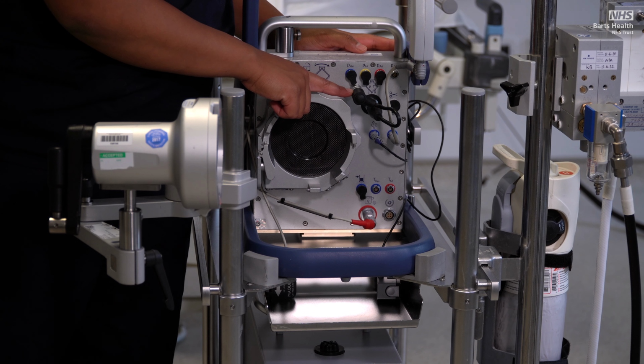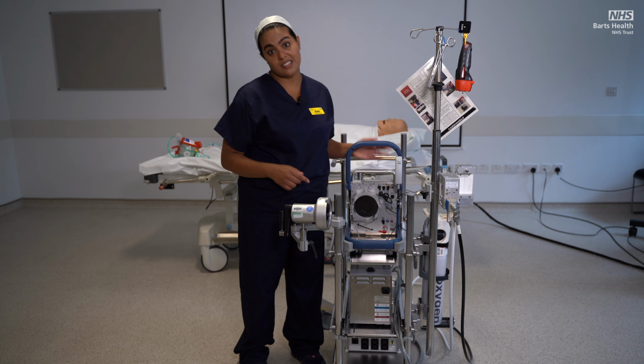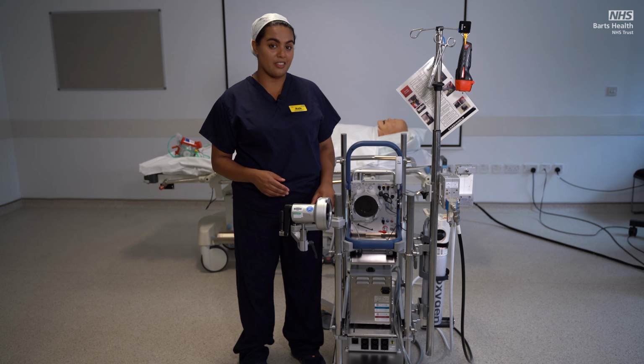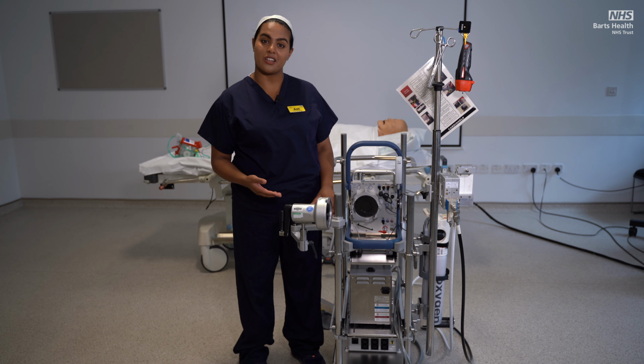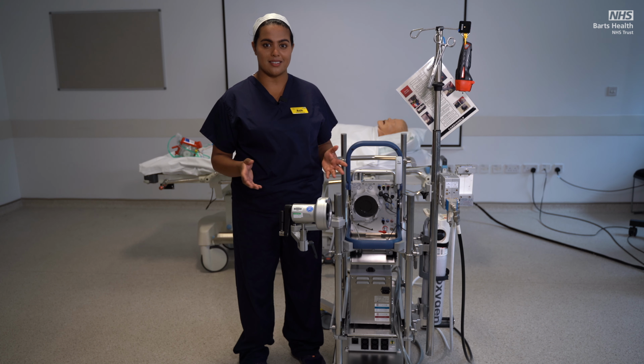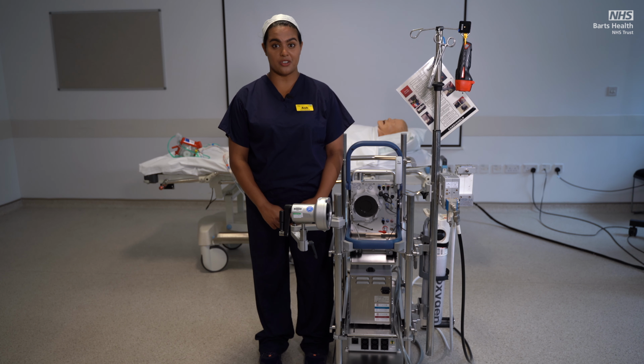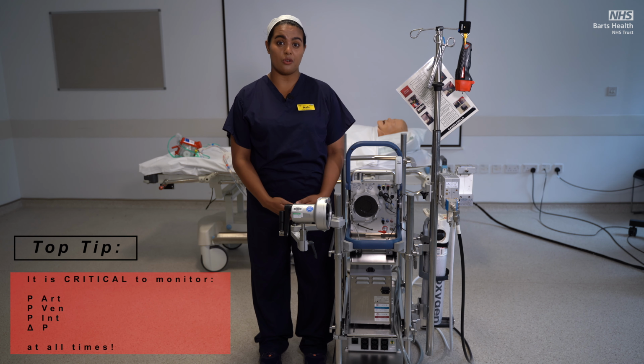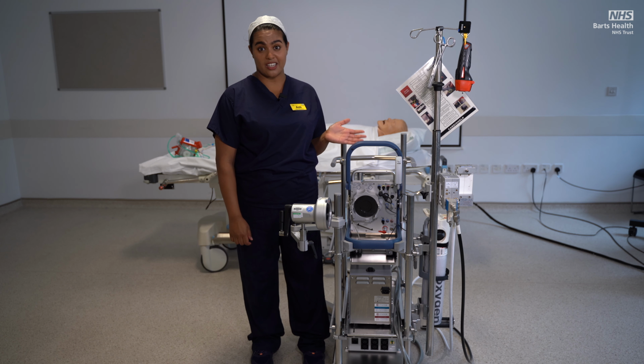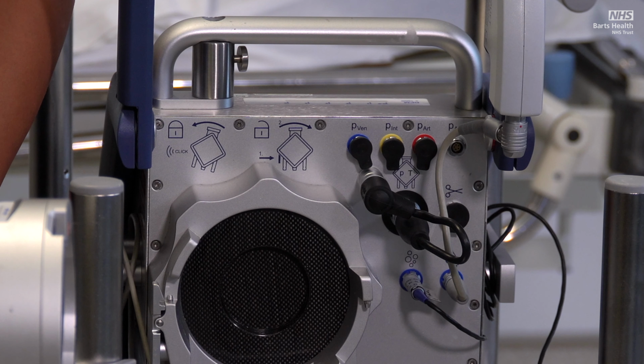This is the Cardiohelp integrated pressure monitoring cable, which measures the ECMO pressures at 3 different points: the venous pressure, also known as the pre-oxygenator pressure, the arterial pressure, also known as the post-oxygenator pressure, and the internal pressure, also known as P-int. In the event that the integrated pressure monitoring cable reads unreliably or is unavailable, these pressures can be transduced externally. It is critical that the pressures are always transduced during an ECMO run to ensure therapy is within safe parameters. Pressures from the console can be externally transduced from these 3 points, which are color-coded for clarity.